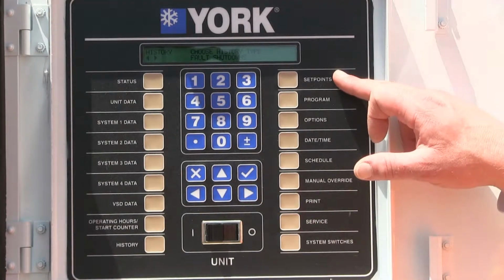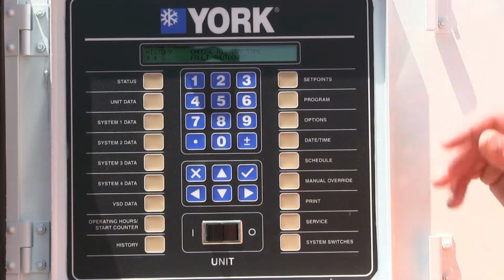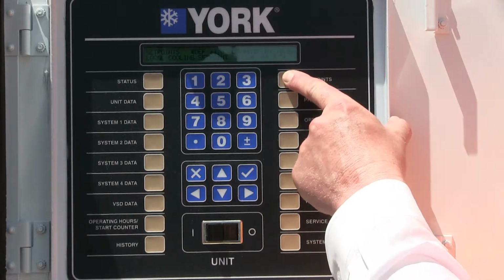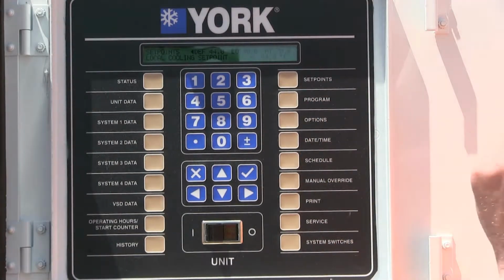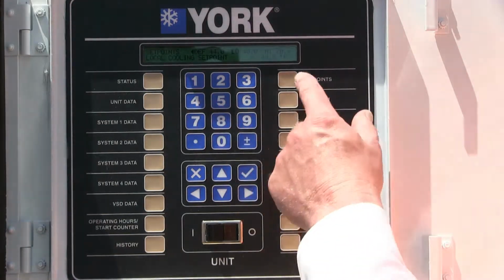And then on your right side, the most commonly used button is going to be your set point. So if you push your set point, you'll note that this is set up for comfort cooling. It says a low of 40 degrees, a high of 70. It's currently set at 44 degrees. We want to chill the water down to 44. And that's the only thing we have the set point.